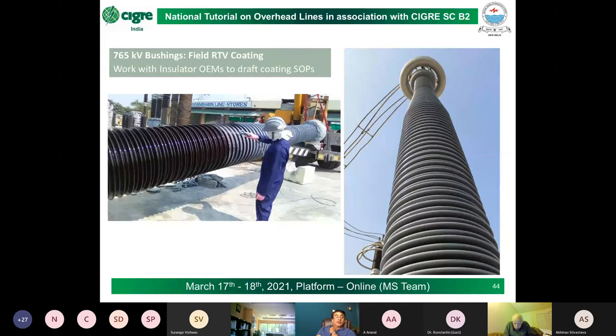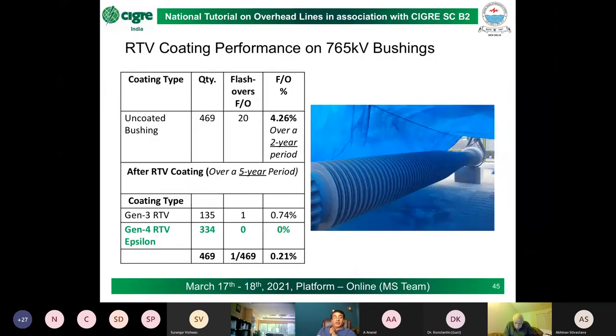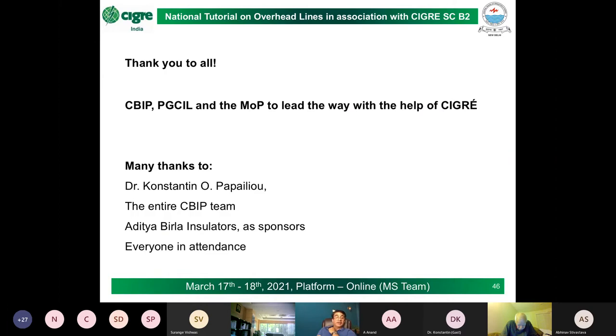This is used on 765 kV bushings all across Power Grid, about 40-odd locations. Between the uncoated and coated bushing, we found approximately a 4% flashover per 2 year period, whereas after the Gen 4 coating, this came down to 0% over a 5 year period. So I would say generally these are highly successful here.